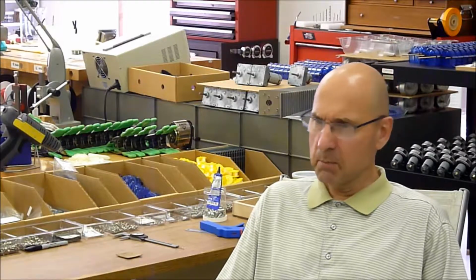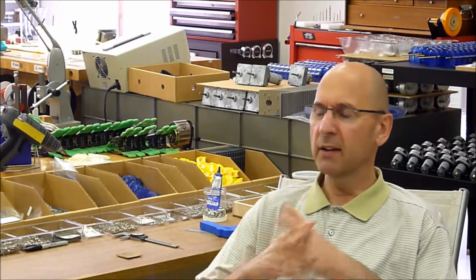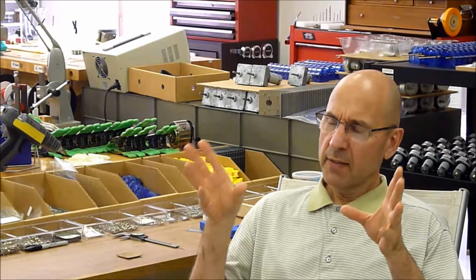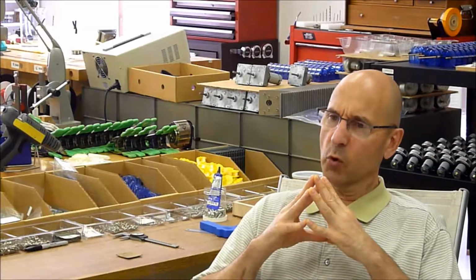So I love to troubleshoot. So the first thing I looked at is, okay, so the wire is kind of melted and charred, which tells me that there was probably too much current going through that wire. And the breaker was not sized properly. I think it was a 20 amp breaker, and it should have been a 15 based on the wire size. Completely another topic. But then I looked at how many lights were out at that particular time. And then let's put Ohm's Law to work. So I counted the number of light fixtures. Each light fixture had 4 light bulbs.